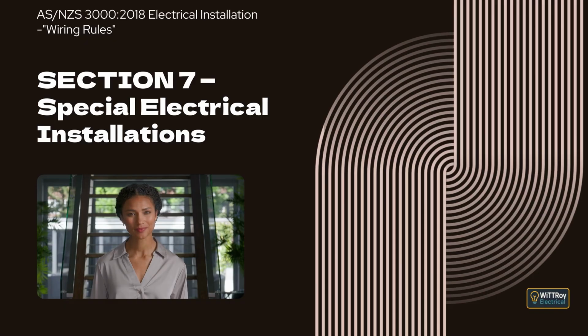Clause 7.3.2 Selection and installation of system. This clause explains that the selection, installation and control of electrical equipment forming part of an electricity generation system must comply with the relevant standards for the type of system being installed. It explains that engine-driven generating sets, standalone power systems, battery systems, photovoltaic array systems and inverter systems each have specific standards that must be followed so that the system operates safely and correctly. Clause 7.3.3 Control. This clause explains that an electricity generation system must be controlled by a main switch or switches located at the installation switchboard where the system connects to the installation.